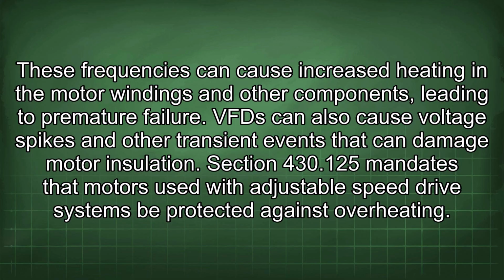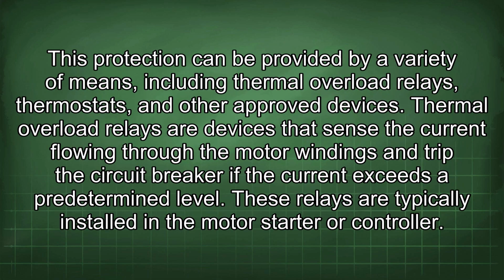VFDs can also cause voltage spikes and other transient events that can damage motor insulation. Section 430.125 mandates that motors used with adjustable speed drive systems be protected against overheating. This protection can be provided by a variety of means, including thermal overload relays, thermostats, and other approved devices.